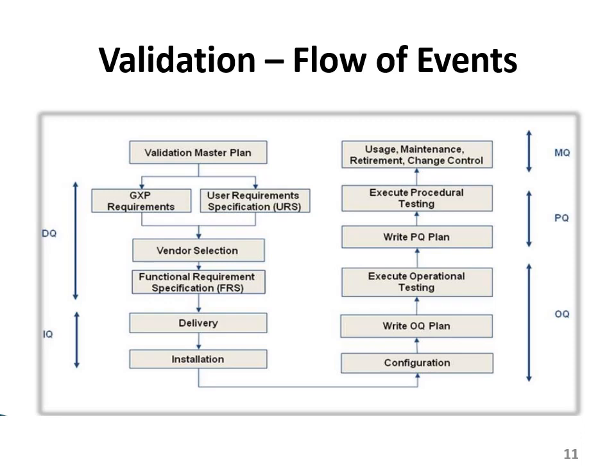Last one is MQ. I haven't given MQ in the steps in the previous slide, but MQ is the maintenance qualification. When you are using some machine, some instrument, definitely the maintenance is very important. So you have to maintain the machine, the instrument, the equipment, and for that, usage, maintenance, retirement, change control, each thing is important.